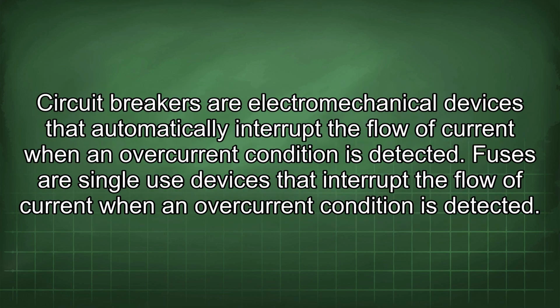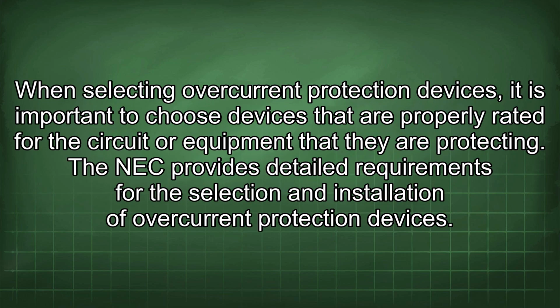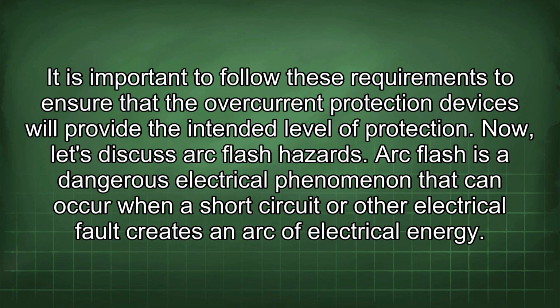Circuit breakers are electromechanical devices that automatically interrupt the flow of current when an overcurrent condition is detected. Fuses are single-use devices that interrupt the flow of current when an overcurrent condition is detected. When selecting overcurrent protection devices, it is important to choose devices that are properly rated for the circuit or equipment that they are protecting. The NEC provides detailed requirements for the selection and installation of overcurrent protection devices. It is important to follow these requirements to ensure that the overcurrent protection devices will provide the intended level of protection.